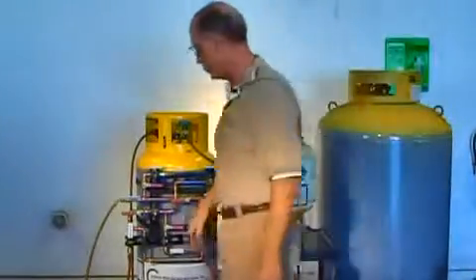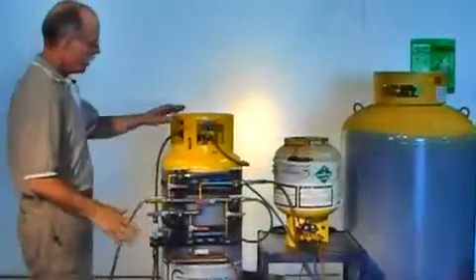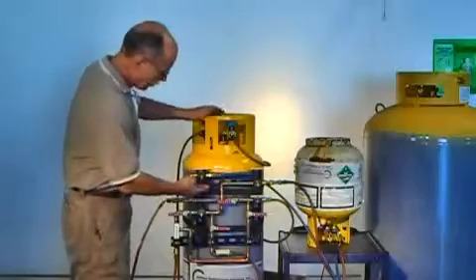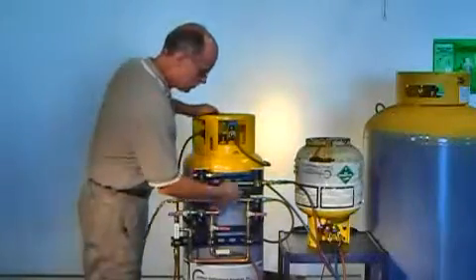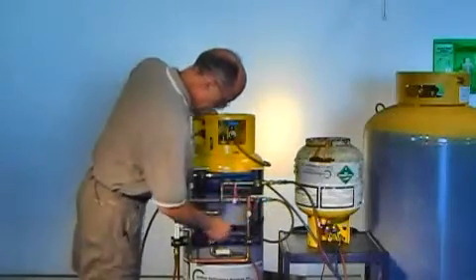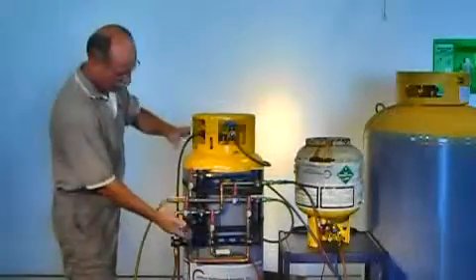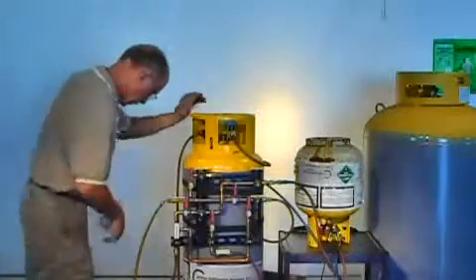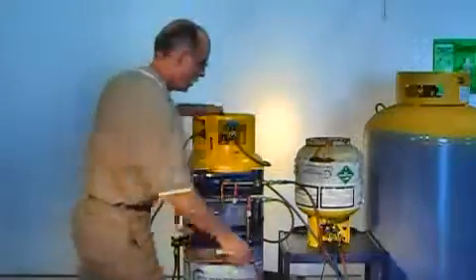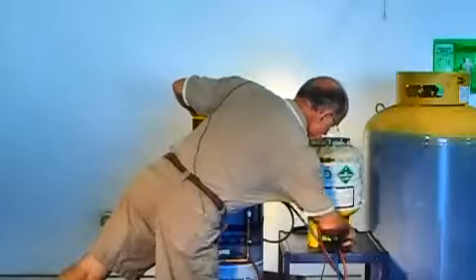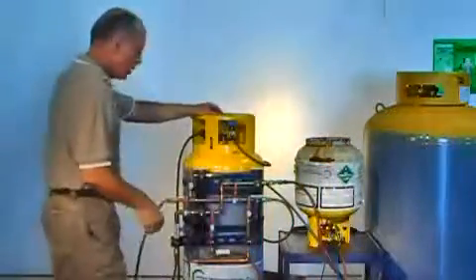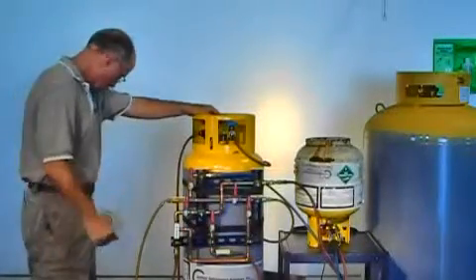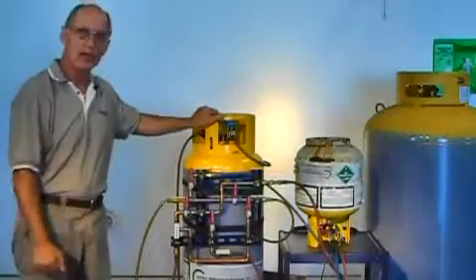Okay the very next part would be to say that I again want to understand that I'm going to have to take the liquid out of this first. So when I go to liquid without rhyme or reason all these handles must be up. I've got all five handles up. I'm ready to take the liquid out of that can. I'm going to start my recovery unit again. I'm going to open these two valves. Right away my sight glass fills up. And we'll start our timer to see how long it takes to get that liquid out of there.